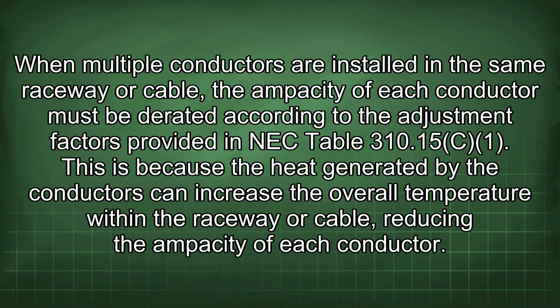When multiple conductors are installed in the same raceway or cable, the ampacity of each conductor must be derated according to the adjustment factors provided in NEC Table 310.15(C)(1). This is because the heat generated by the conductors can increase the overall temperature within the raceway or cable, reducing the ampacity of each conductor.